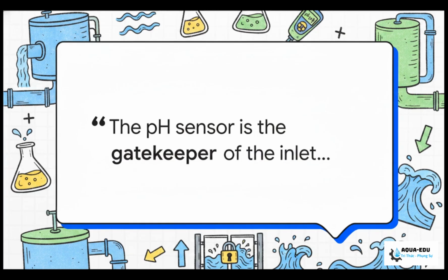I really want to leave you with this final, incredibly powerful lesson from the SOP. The pH sensor is the gatekeeper of our entire treatment plant. Think about it. A tiny error at the inlet amplifies into a massive, disastrous violation at the outlet. Because of that, you can never completely trust the online value without periodic manual verification using your handheld meter. It's your plant, brothers. So I have to ask you, when was the last time you manually verified your gatekeeper? Think about that on your very next shift.